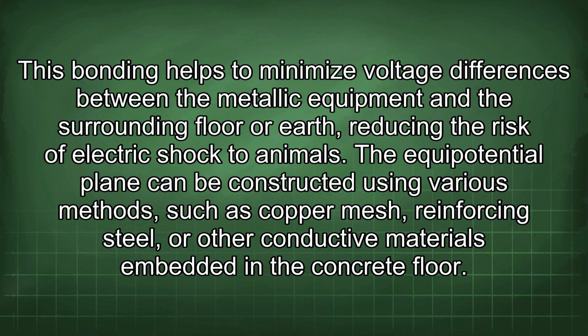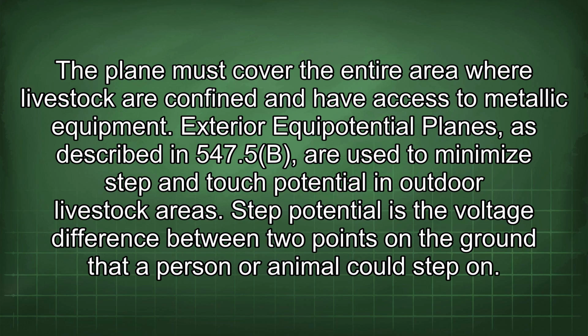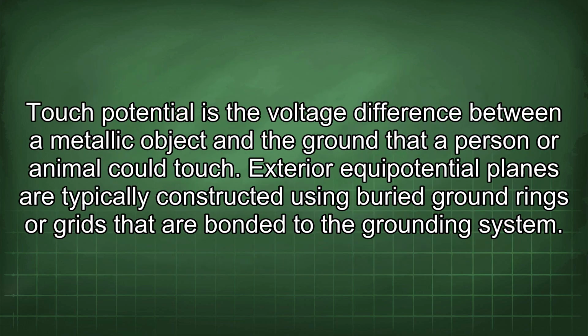The equipotential plane can be constructed using various methods, such as copper mesh, reinforcing steel, or other conductive materials embedded in the concrete floor. The plane must cover the entire area where livestock are confined and have access to metallic equipment. Exterior equipotential planes, as described in 547.5(B), are used to minimize step and touch potential in outdoor livestock areas. Step potential is the voltage difference between 2 points on the ground that a person or animal could step on. Touch potential is the voltage difference between a metallic object and the ground that a person or animal could touch.